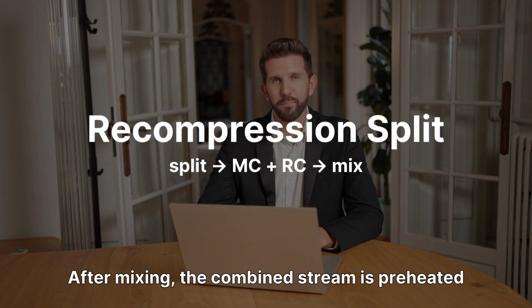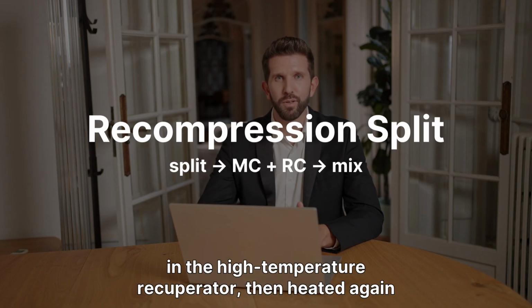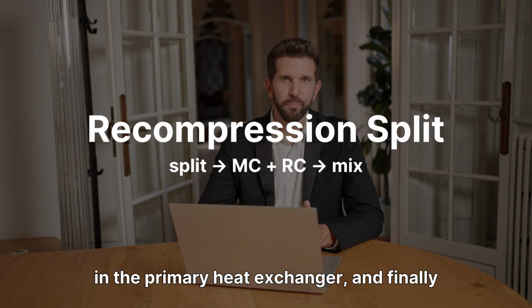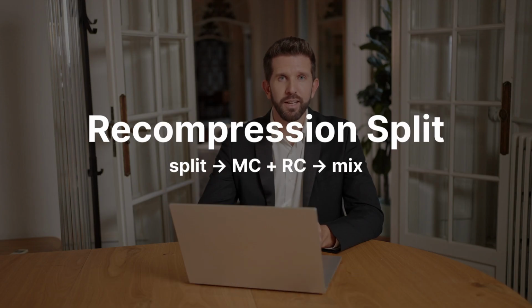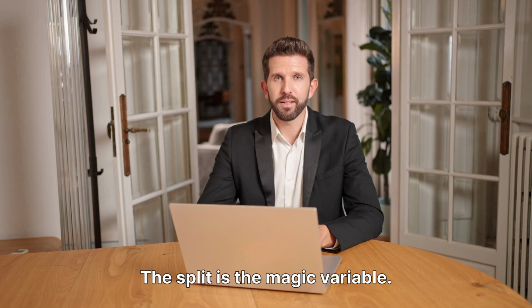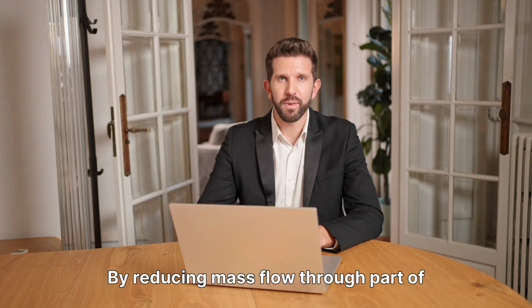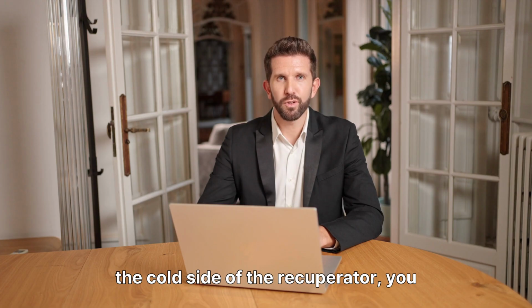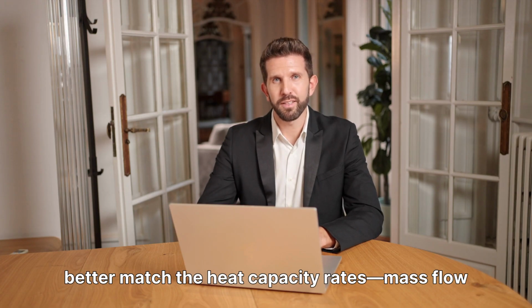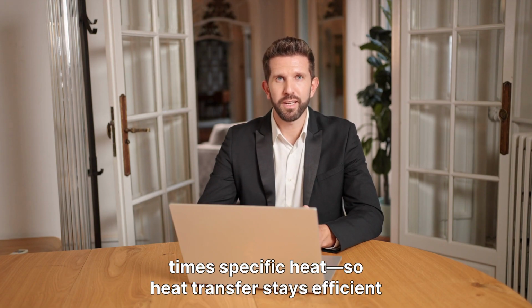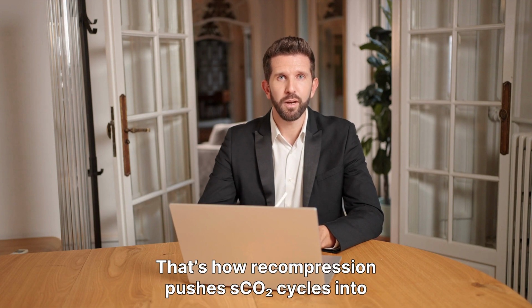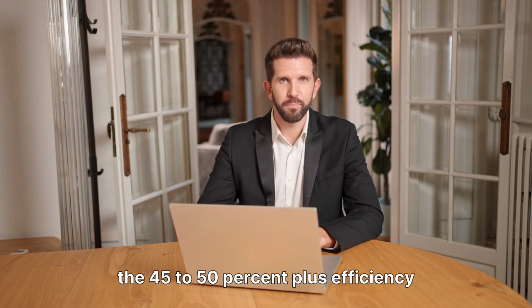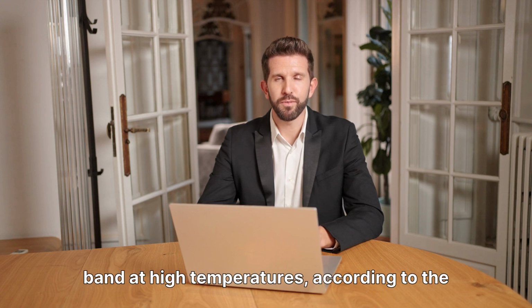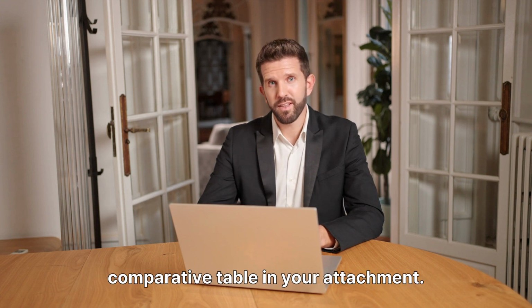After mixing, the combined stream is preheated in the high-temperature recuperator, then heated again in the primary heat exchanger, and finally expanded through the turbine. The split is the magic variable. By reducing mass flow through part of the cold side of the recuperator, you better match the heat capacity rates, mass flow times specific heat, so heat transfer stays efficient and the pinch point is reduced. That's how recompression pushes SCO2 cycles into the 45 to 50% plus efficiency band at high temperatures, according to the comparative table in your attachment.